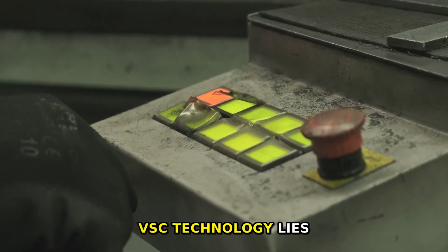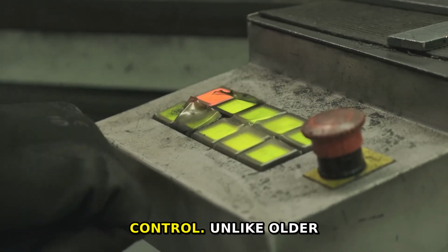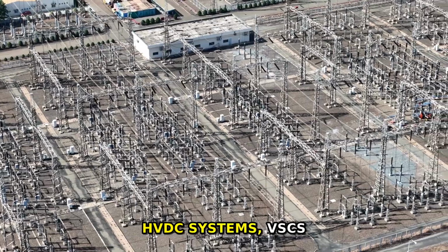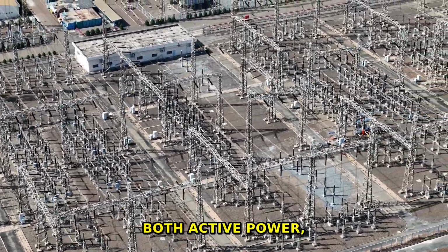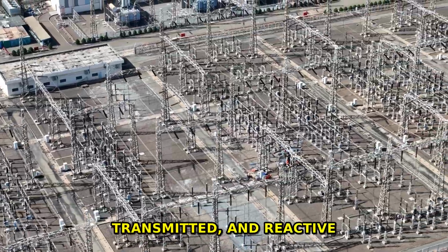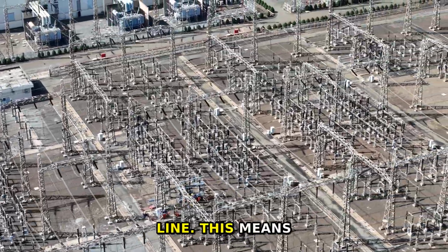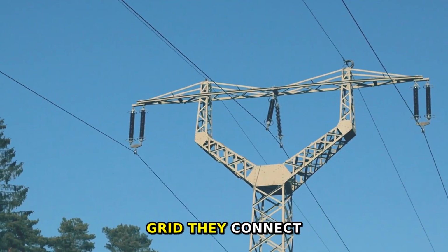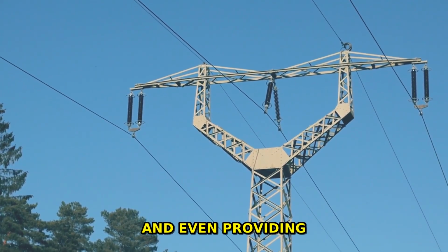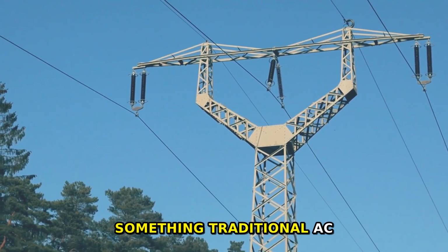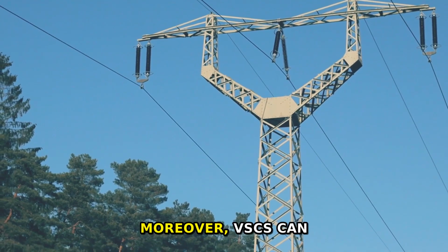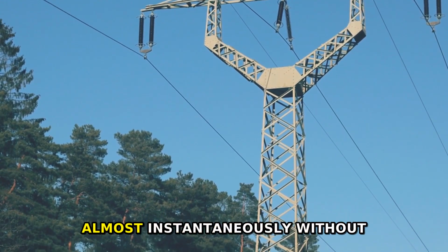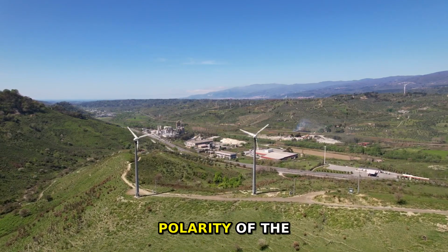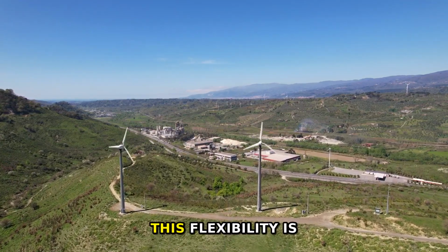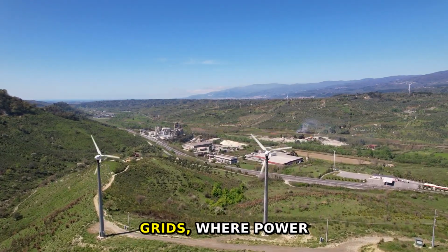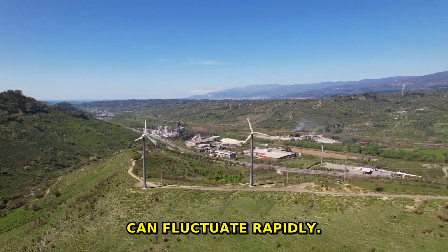The brilliance of VSC technology lies in its precise control. Unlike older HVDC systems, VSCs can independently control both active power, the useful power transmitted, and reactive power at either end of the line. This means they can actively support the AC grid they connect to, improving stability and even providing reactive power compensation, something traditional AC lines struggle with. Moreover, VSCs can reverse power flow almost instantaneously without reversing the voltage polarity of the DC line itself. This flexibility is crucial for modern grids, where power generation from renewables can fluctuate rapidly.